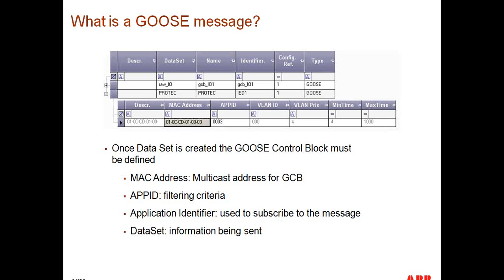One of the questions that I received is, how come we can actually freely allocate the MAC address for a Goose message? Well, the source MAC address, the MAC address that you see when you look at the communications package, is who is sending the message. The message is being sent by the relay, and that MAC address is unique because it comes from the hardware Ethernet adapter of that particular IED.